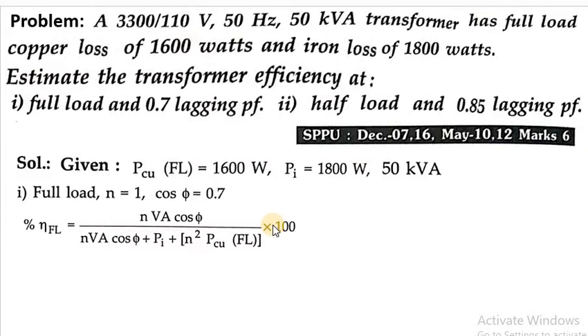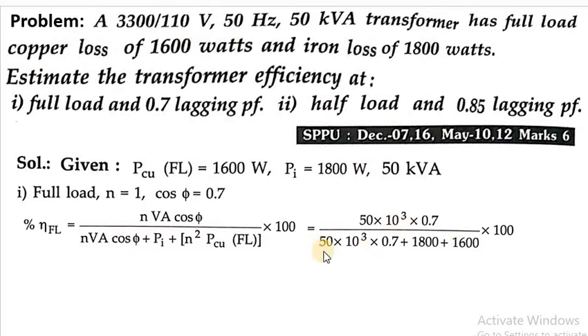So n equals 1, VA rating is 50 × 10³, cos φ is 0.7, iron loss is 1800 watts, and n² equals 1, so P_cu at full load is 1600 watts. Substituting: (1 × 50 × 10³ × 0.7) divided by (1 × 50 × 10³ × 0.7 + 1800 + 1600) times 100.